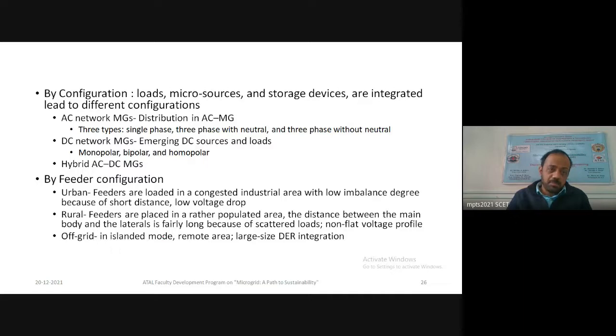Then comes classification by feeder configuration. Urban feeders are loaded in congested industrial areas with low imbalance degree because of short distance, leading to low voltage drop. Rural feeders are placed in more scattered areas compared to urban, and the distance between the main body and lateral is fairly long; because of the scattered load, a non-flat voltage profile is experienced. So in urban areas there is more low voltage drop, while in rural cases there is a non-flat voltage profile experienced by consumers.